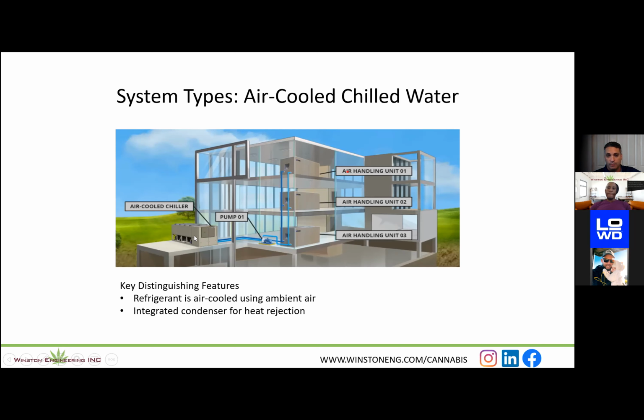The air-cooled part of this happens when you get the warm water back from the building and you run it through these fans and you blow air across that water, or across the pipes with the water in it, to effectively reject the heat out to the atmosphere. So the key distinguishing feature for this particular method of chill water is that the refrigerant is air-cooled using the ambient air. So just by thinking of that, if you're in a place like I am in Dallas, Texas, where it could be 100 degrees on any given day, you're probably not going to get very good efficiency out of your air-cooled chill water. In the cooler climates, you definitely will.